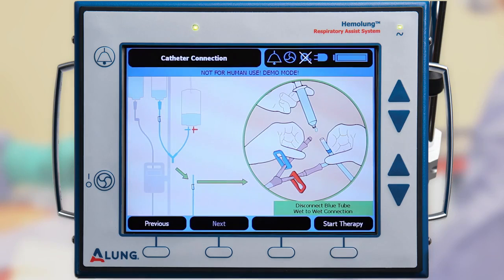To begin therapy, check for air in circuit and check for secure connections. Connect oxygen if selected. Ensure seal flush is running at 30 milliliters per hour. Ensure all clamps are open. Lock the wheel casters. Press Start Therapy.